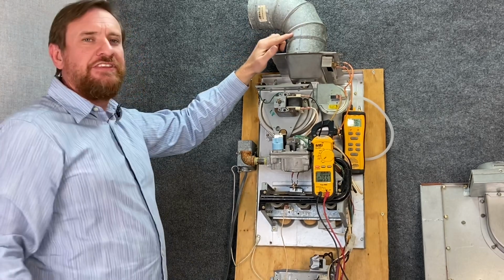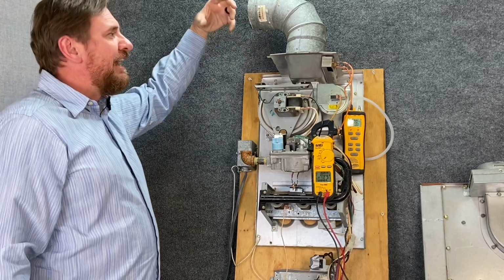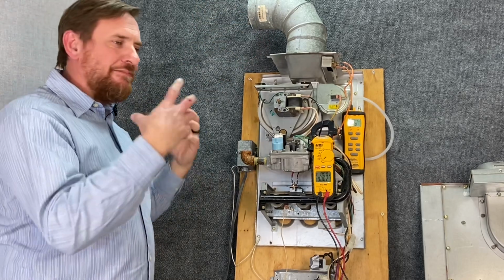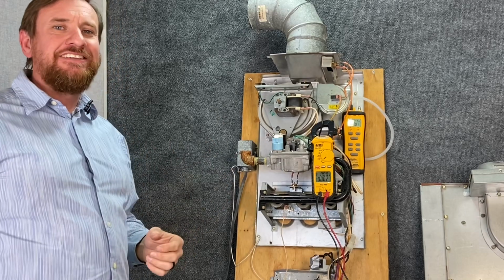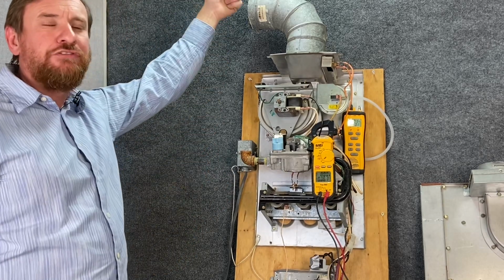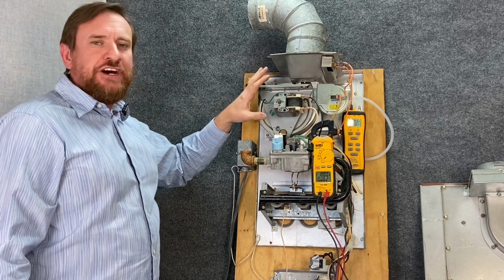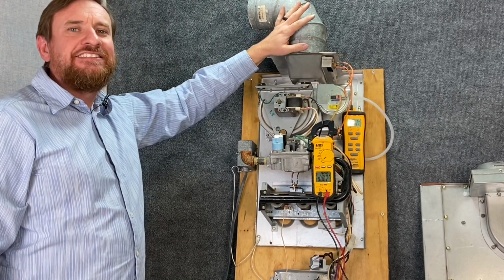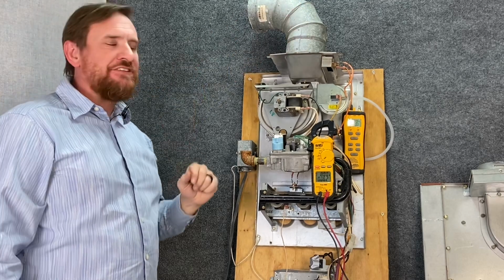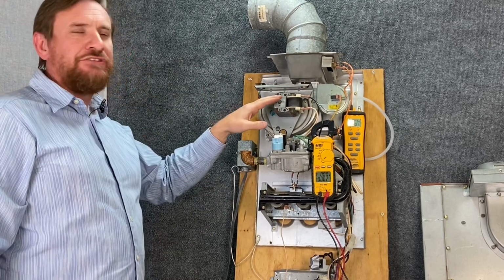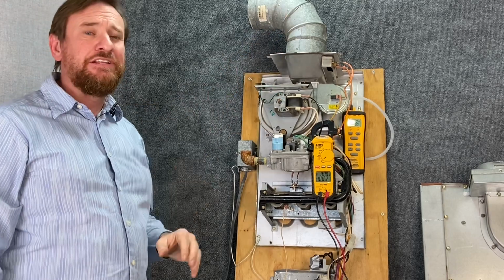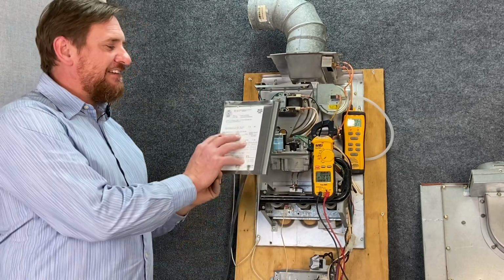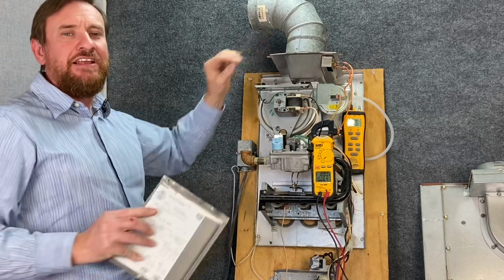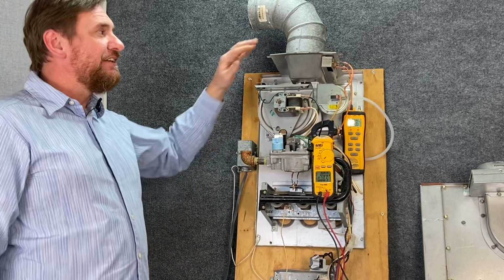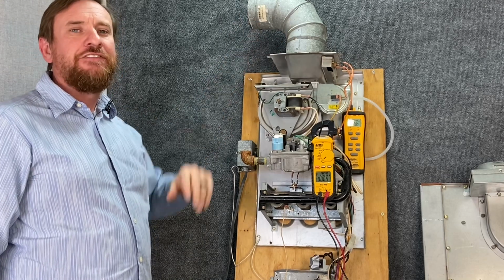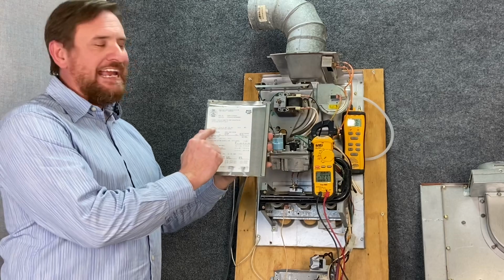If you hook the manometer to this, you would see that it's negative pressure. It's because of the natural convection. As the molecules are moving faster, they're becoming less dense and lighter, and they're traveling up and out of this flue pipe. This fan motor does not force the combustion gases out of this flue pipe. I've had technician after technician claim that because it has this inducer fan motor, it's forcing the gases out, and that's simply not true. You need to read, and if it says it's a category 1, it is a natural draft. Now they do make a few category 3, still non-condensing, that's positive pressure, but they're very few and far between. Read the label on that furnace and see what category it is.